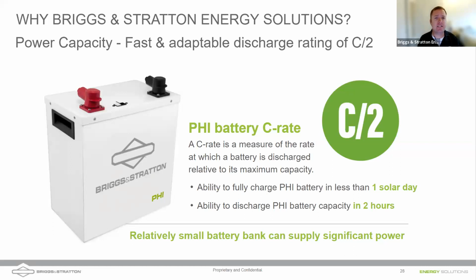If we had lead acid batteries with maybe a C/20 or C/10 rate, or if you're really pushing them, maybe a C/5 rate, you'd have to run the generator for 5, 10, or 20 hours to really charge the batteries. Even with a huge generator with a lot of power, you can't push it into the batteries too quickly or you'll damage them.